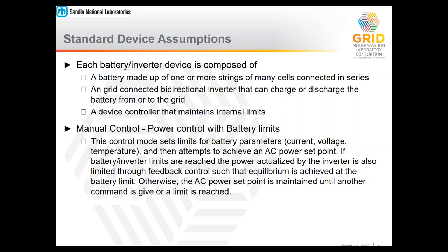And this is the idea that you set battery limits based on current voltage and temperature, and then attempt to achieve an AC power set point within those limits. If you reach those limits before reaching the AC power set point, the AC power stops at that limit. So if you, say, wanted to supply 20 kilowatts to the grid, but had a low voltage limit of, say, 48 volts, then the system would discharge the battery and try to achieve 20 kilowatts. But if it hit that 48 volts at, say, 10 kilowatts, then it would stop there. So this is important to understanding how the actual battery responds to requests from the grid.